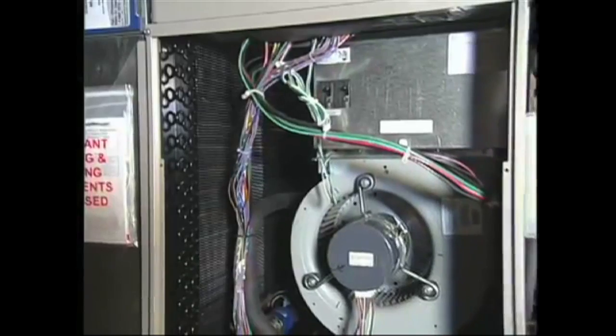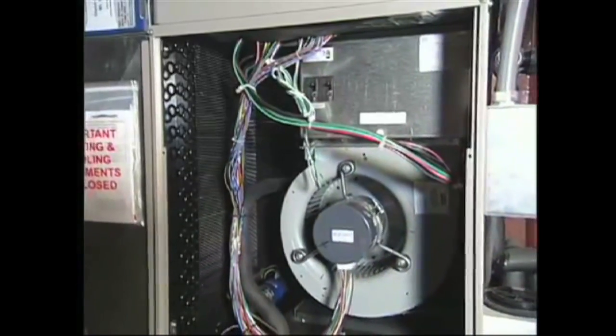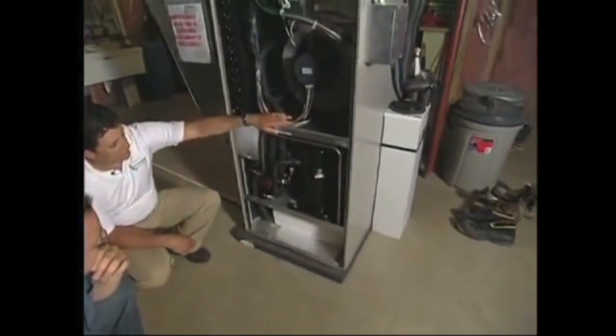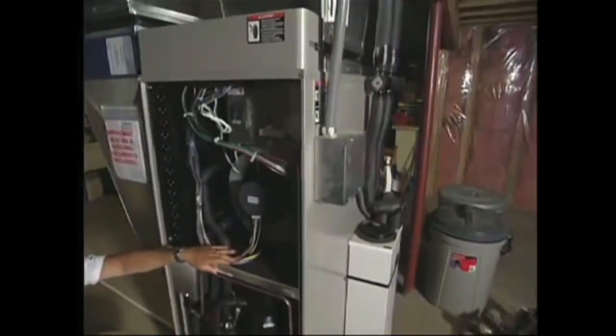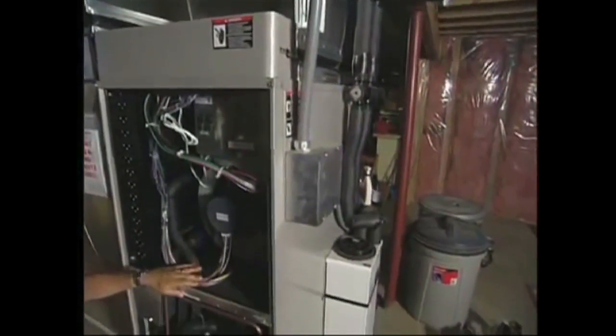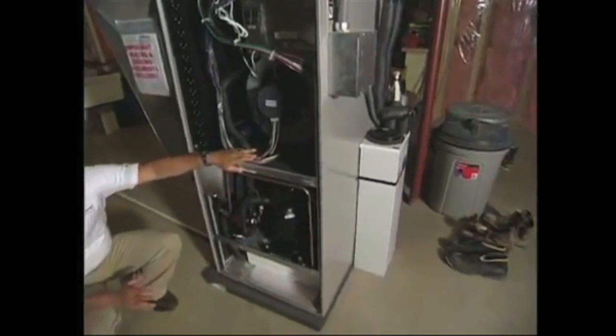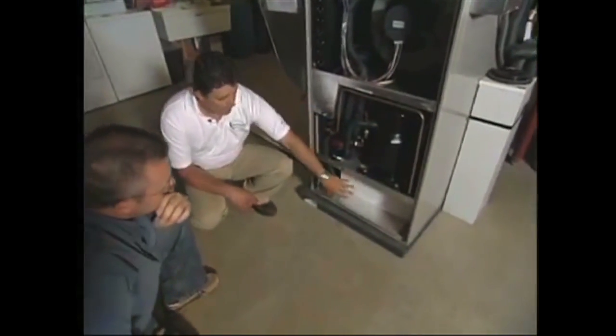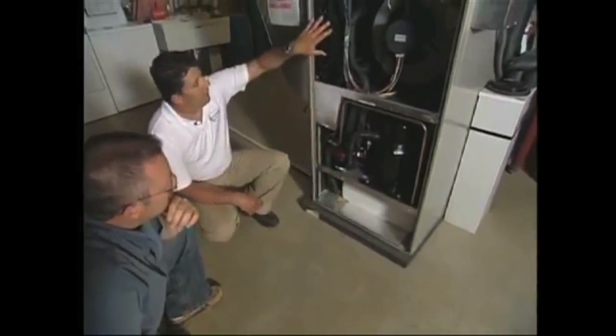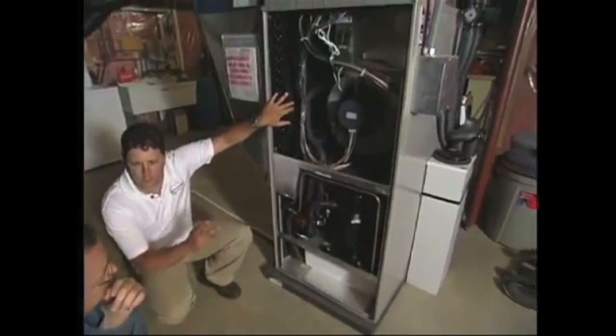Absolutely. Well, this is our brand new Compass Series product from Geocomfort, and there's a lot of innovation in this machine, but we'll go through the actual components and how this works. So really what we have inside the box is three major components: a compressor, a water-to-refrigerant heat exchanger, and an air-to-refrigerant heat exchanger. So two heat exchangers.